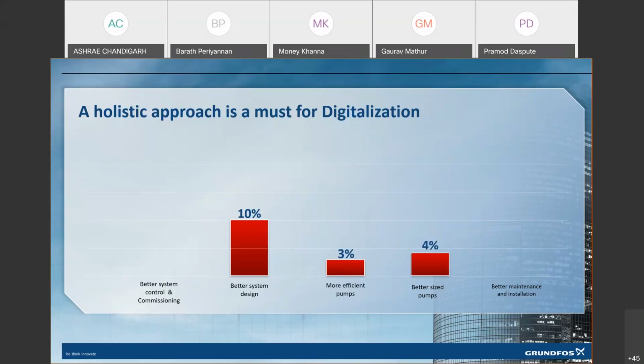And by doing a better selection, you are able to achieve a certain amount of efficiency improvement at the equipment level. You are able to achieve a certain further efficiency when you ensure better maintenance and installation. But what actually makes the difference is better system control and commissioning. And when I say commissioning, it is commissioning and system efficiency control which you do throughout the life cycle and under any load profile of your building. And that is where we say it is the holistic, system-based approach which gives you the platform to go to digitalization.